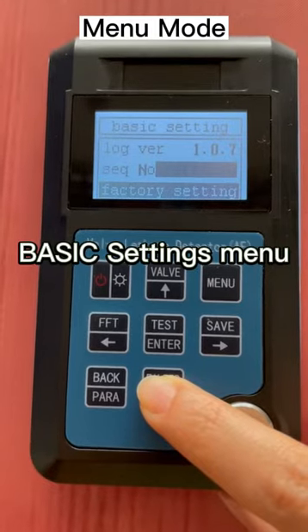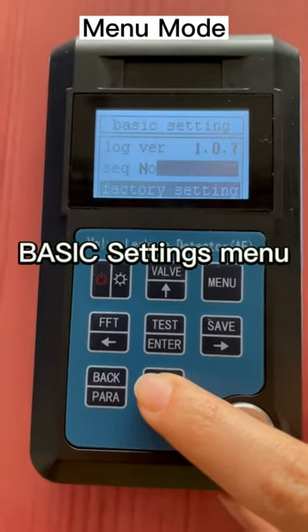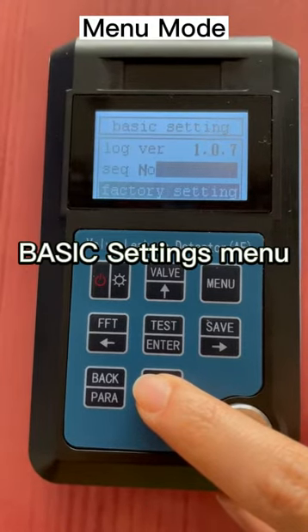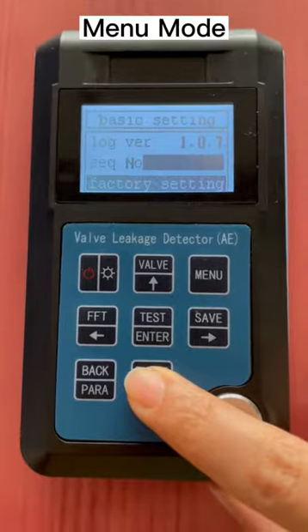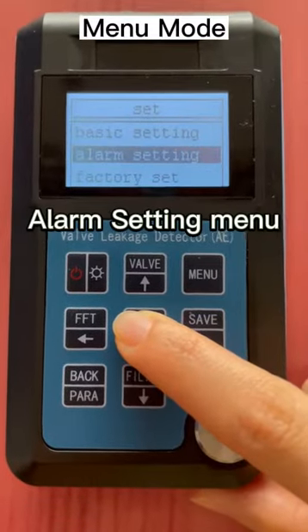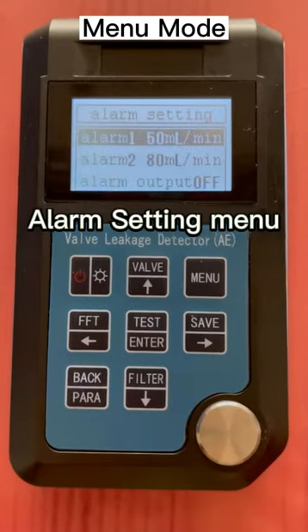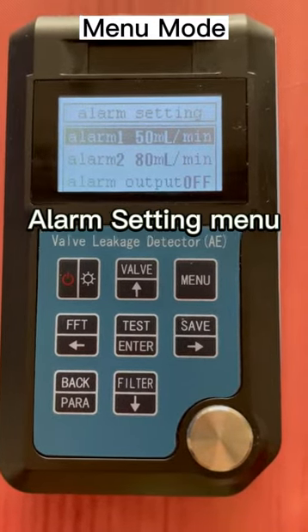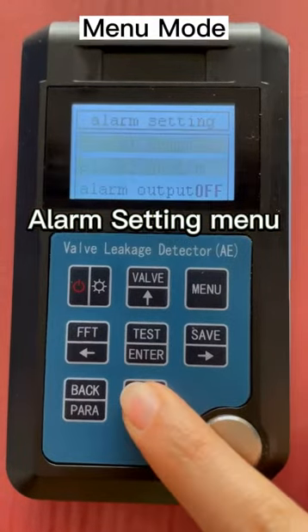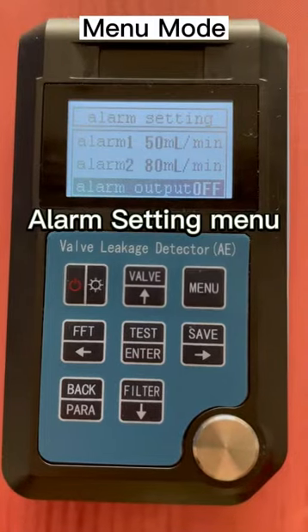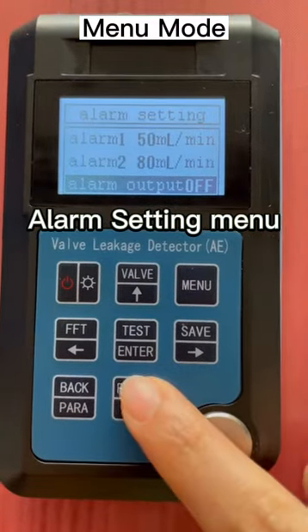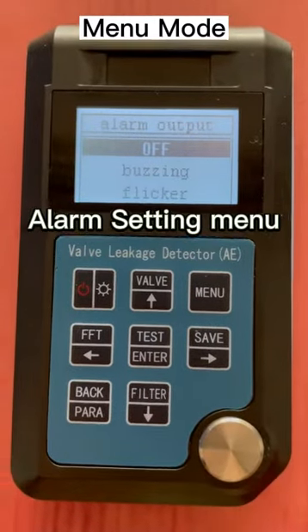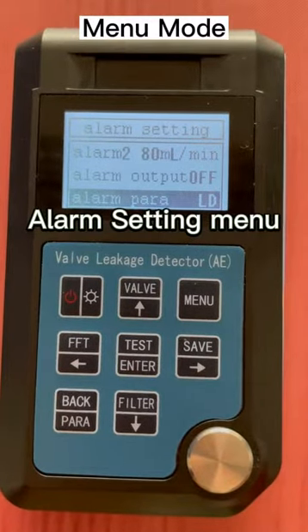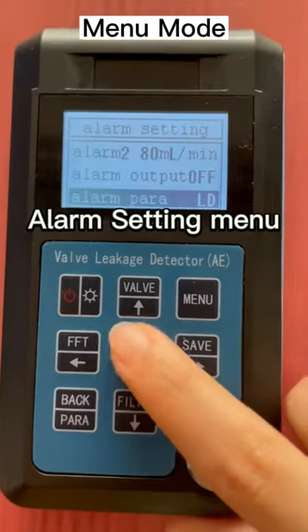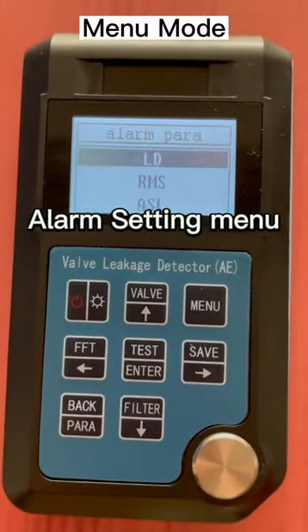If factory settings is selected, it will prompt you to reset to factory settings. After confirmation, all the data will be erased. In the alarm setting menu, it can set level 1 and level 2 alarm values. Alarm output can be turned on or off, and it can choose to output as buzzer or flicker. The alarm parameter is to choose which AE parameter or leakage value to be the alarm reference standard.